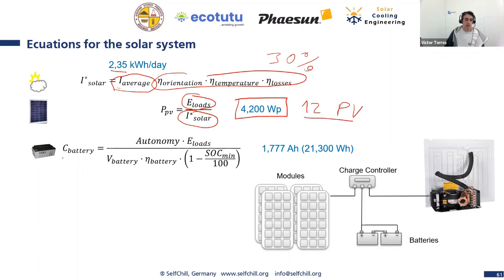What about the battery? The capacity of the battery in amperes hours is calculated like this. You need the electrical load, and here we are using 7.8 kilowatt hour per day. Regarding autonomy, because we are working with the worst case scenario, we don't need any autonomy since we are already calculating the worst case. So autonomy can be 1 day - just the energy we need for this critical day.